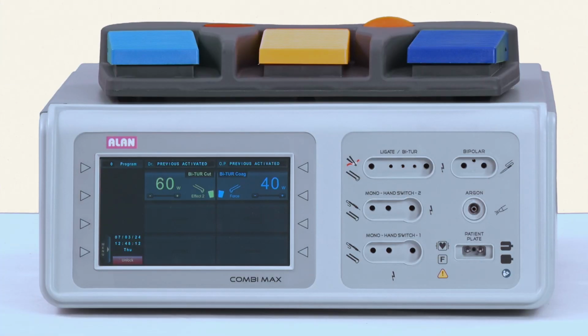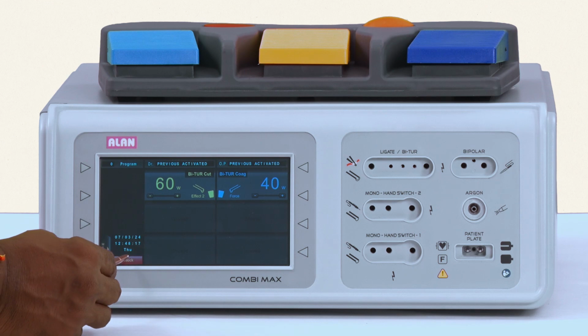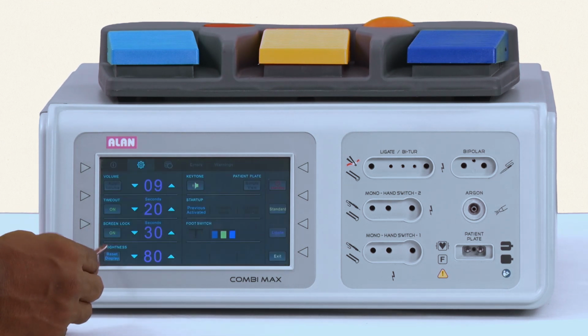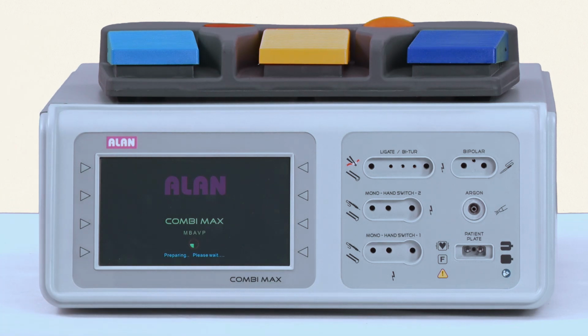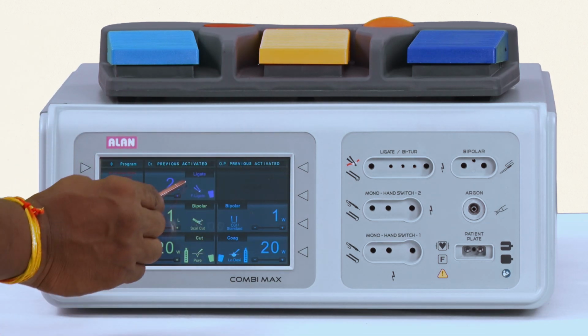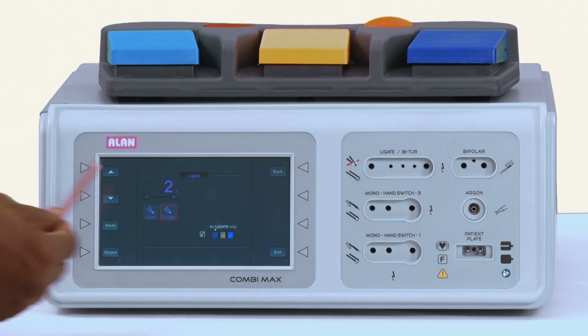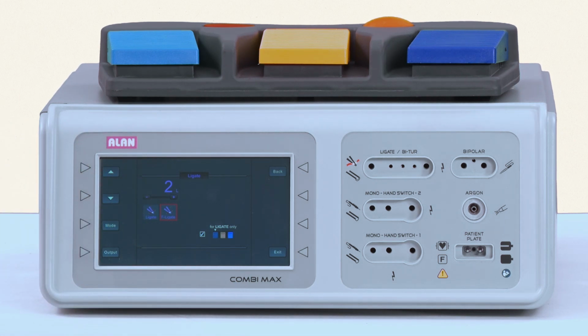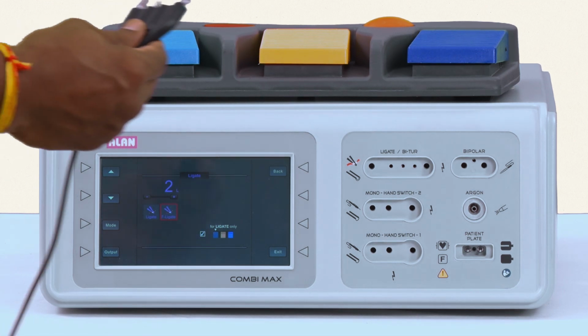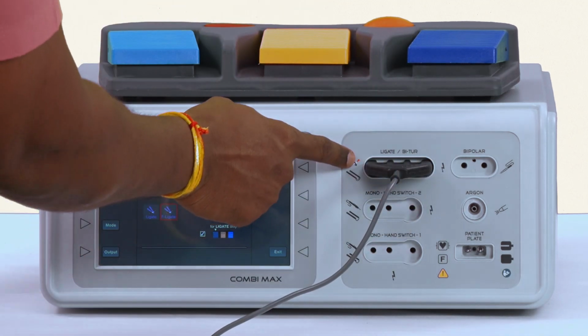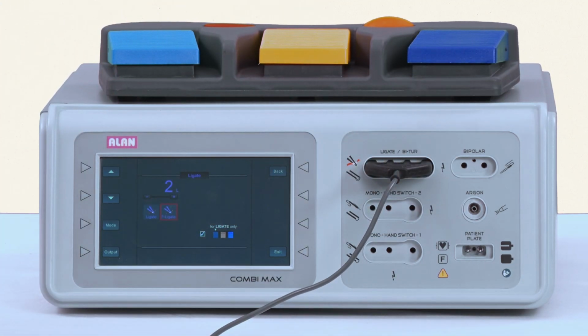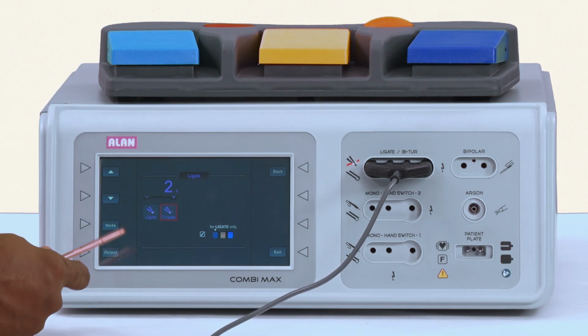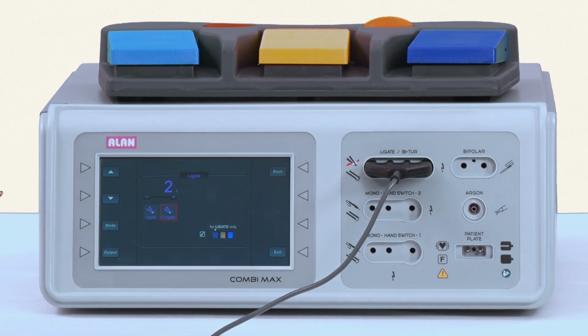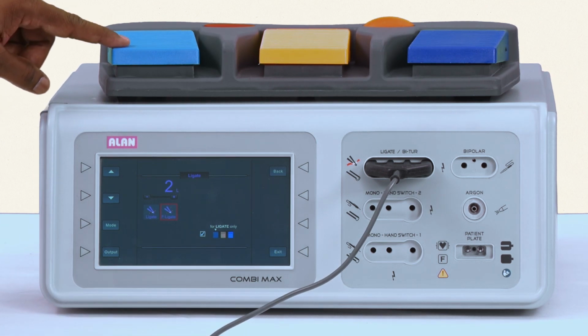You must be in the ligate window to employ a vessel sealing feature in your surgical application. To access it, unlock the screen, go to menu, choose ligate. Once the window is ready, click on this icon, choose the mode and levels as per your instrument, for example 5 mm and 10 mm instrument. Now connect the instrument to this respective port. Now the unit is ready for activation. Combi Max supports both hand and foot activation. For activation with pedal, use the light blue pedal.